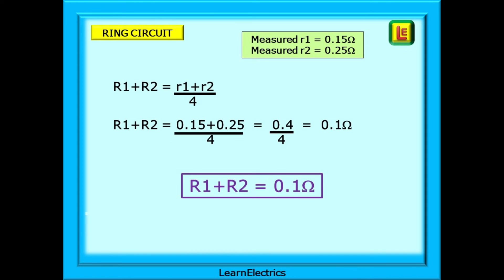Let's look at how we get big r1 plus big r2. R1 plus r2 is calculated by adding together little r1 and little r2 and then dividing by 4. A ring circuit is a parallel circuit. In this example, little r1 is 0.15 ohms and little r2 is 0.25 ohms. 0.15 plus 0.25 is 0.4, and if we divide this by 4, we have an effective resistance of 0.1 ohms. Big r1 plus r2 for this circuit is 0.1 ohms.